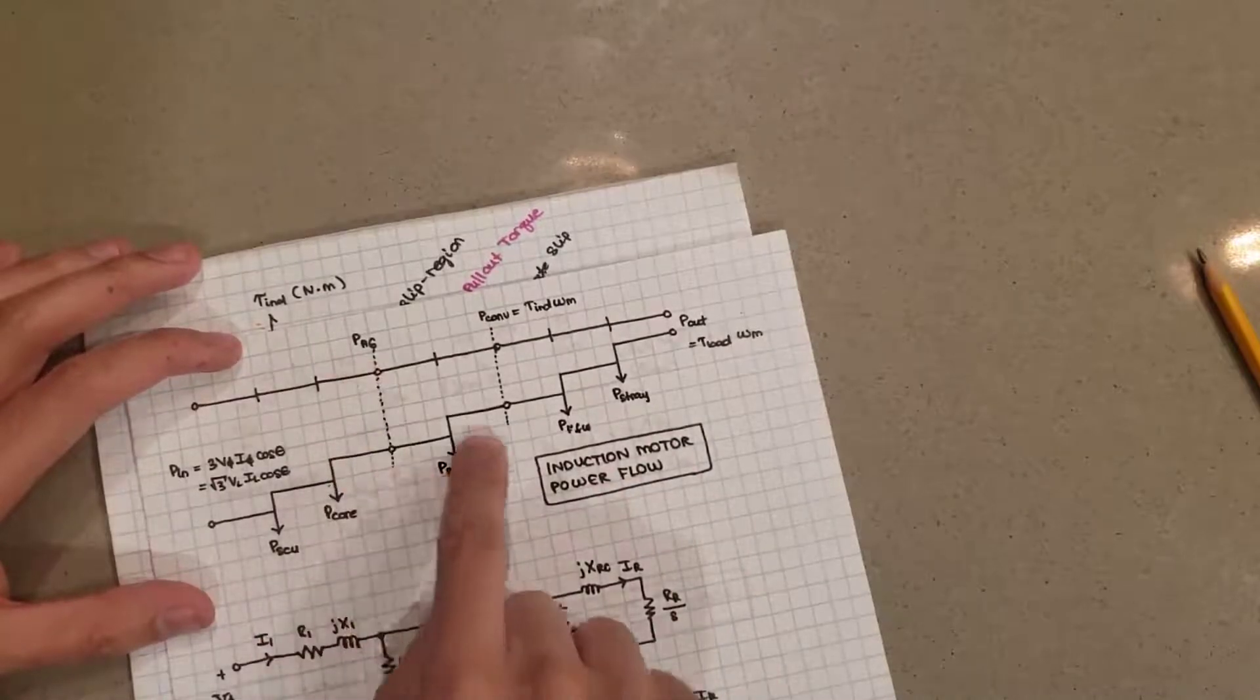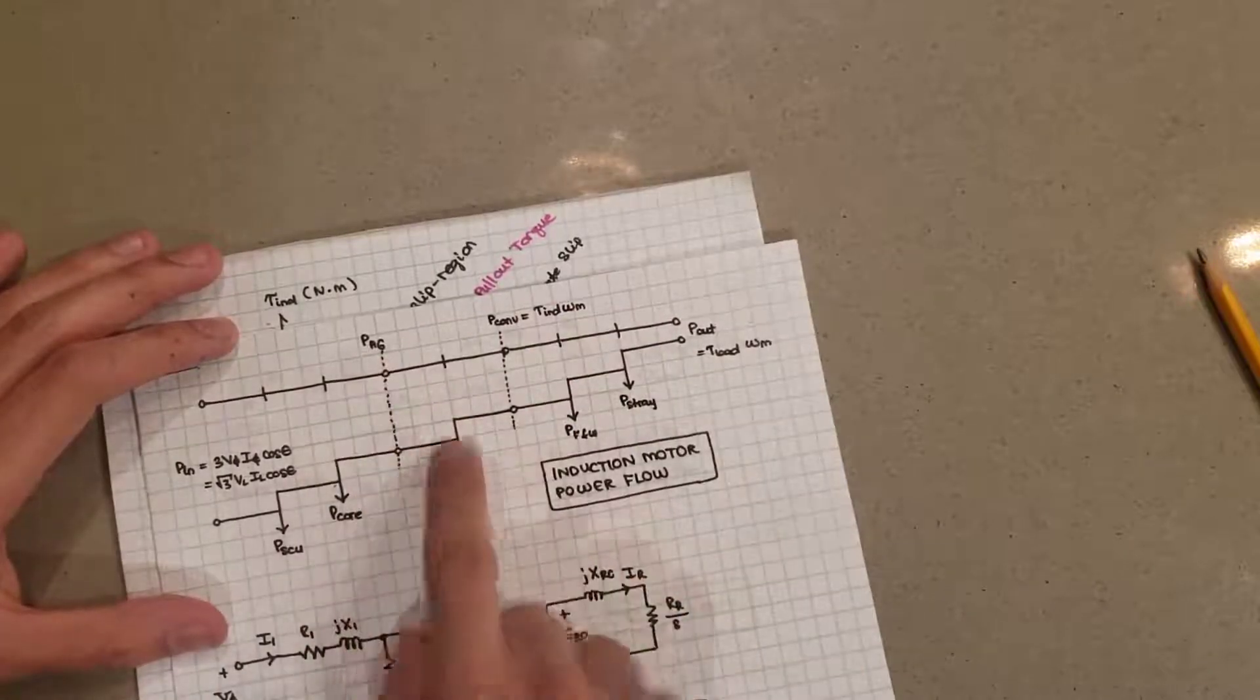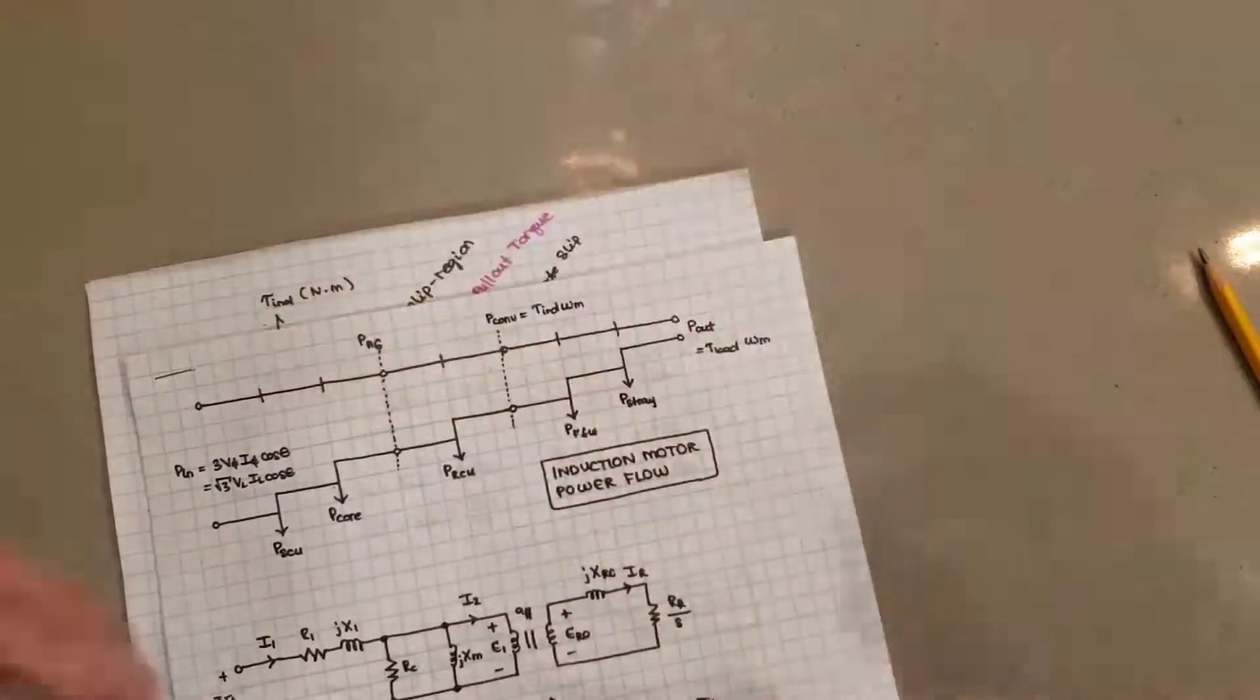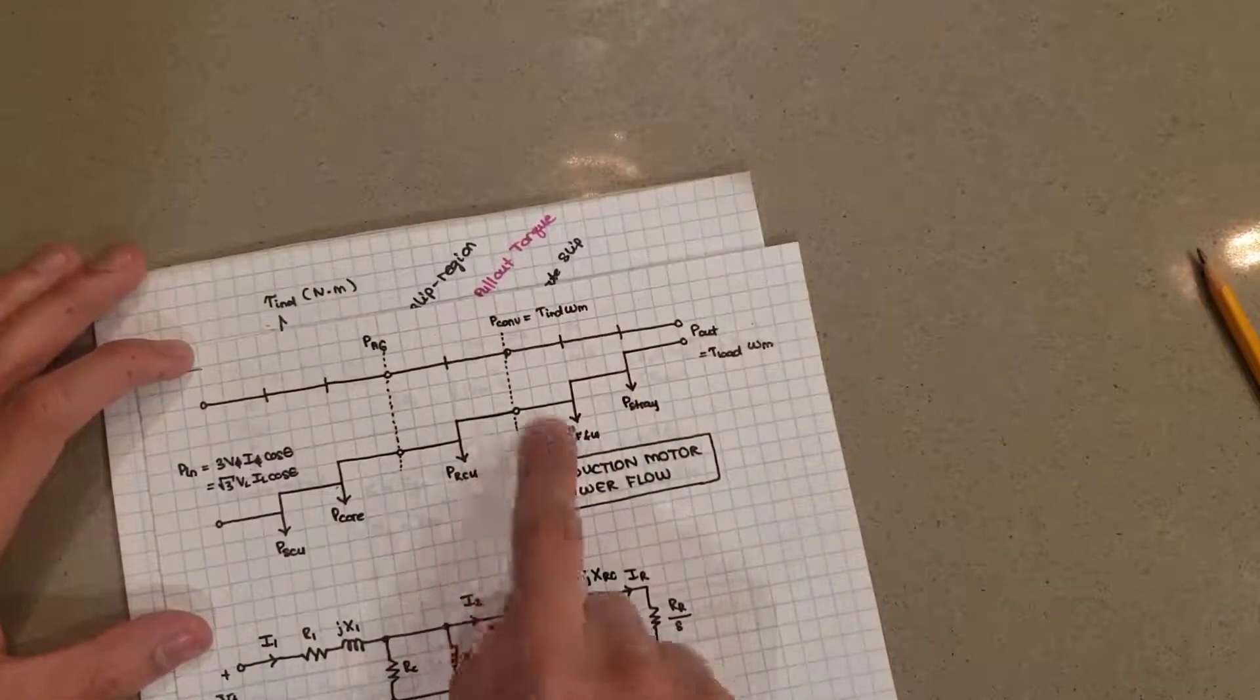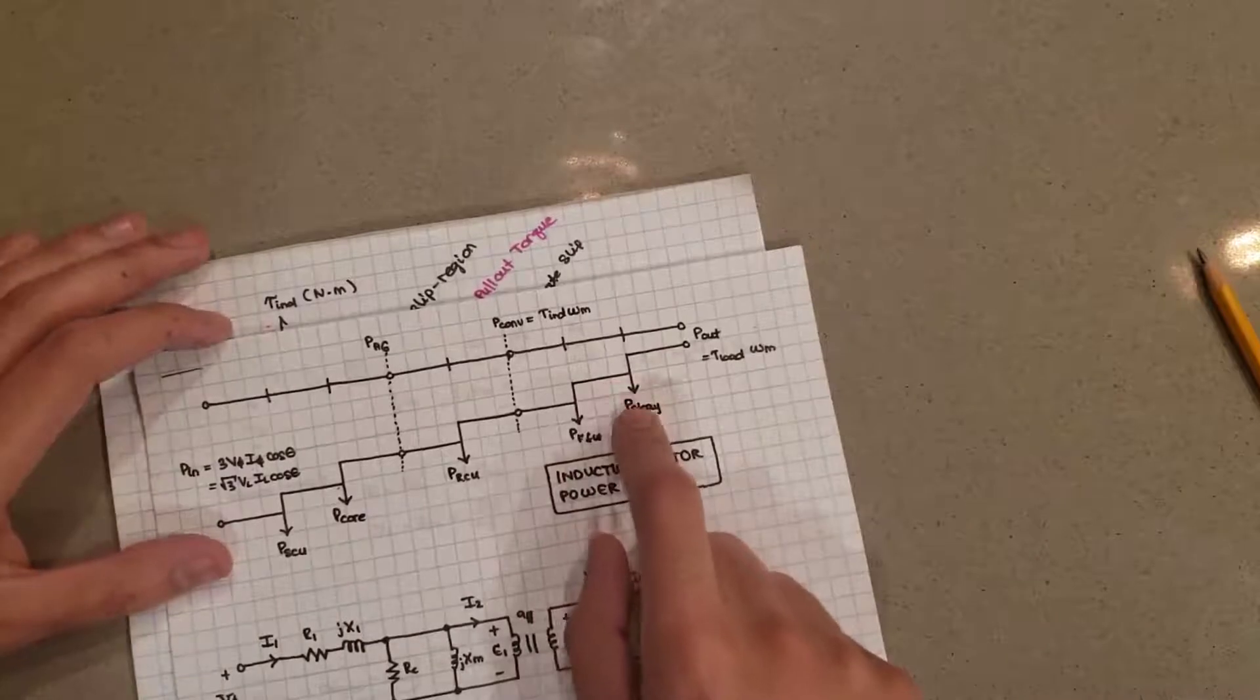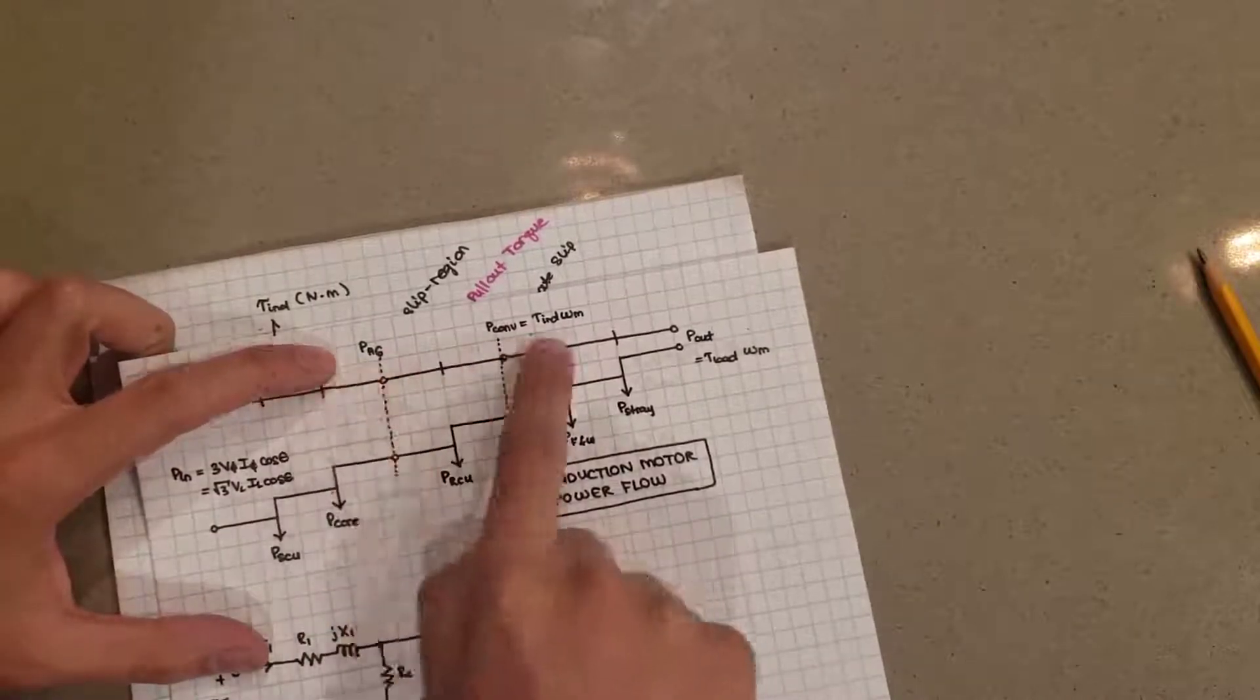However, what happens is, of course, the rotor itself has some resistance. So there's going to be some copper losses in the rotor. So that's going to take away from the air gap power. And then we get to that P converted. P converted stands for how much electrical power is being converted to overall mechanical power. And then we can see that mechanical power, some of that is taken away from friction and windage losses. And then there's some stray losses that we are not able to account for. And that finally leads to the actual power output of the motor, mechanically speaking.